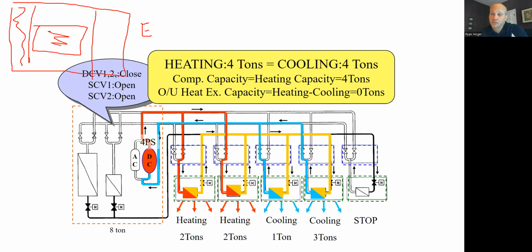So in this case, you will intentionally try to mix exposures. Before I said on most zoning systems, whether it's a heat pump or VAV or whatever, I should say VAV's got some exceptions, but VVT, I wouldn't want to mix interior and exterior. I wouldn't want to mix perimeter, east and west, etc. On a heat reclaim, you want to do that on purpose. So it's the opposite zoning mentality. You want to mix east with west. You want to mix north with south. You want to mix interior and exterior. You want to mix it all so you can get as many zones that want heat at the same moment in time as many zones as want cooling.